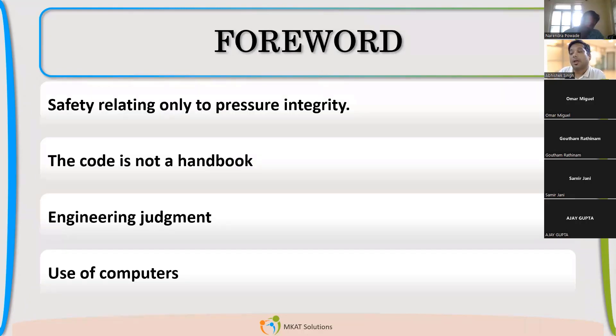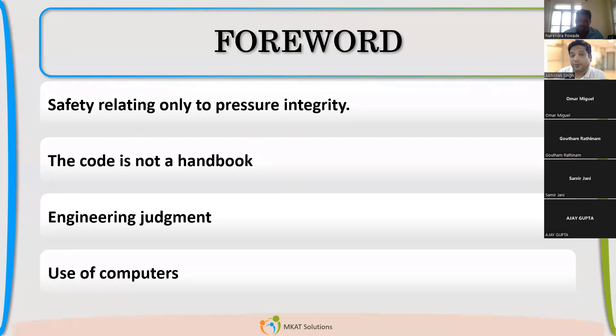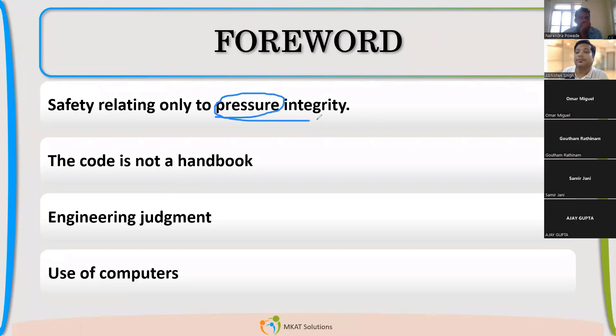Now we are at the foreword. If you have the code with you, please open it and try to read the foreword. If you read the code very carefully, see the first statement — it's talking about the code being related to safety, relating only to pressure integrity. There are lots of different loadings: pressure, temperature, wind, seismic, piping loads, equipment loads, platforms, ladders. But ASME Section 8 Division 1 is focused on pressure integrity.